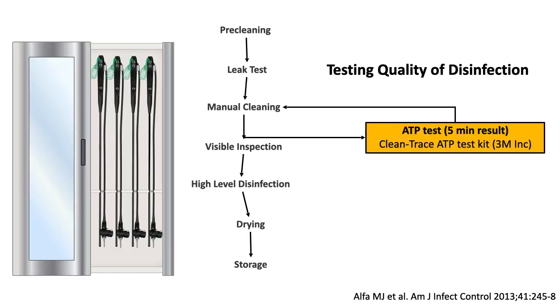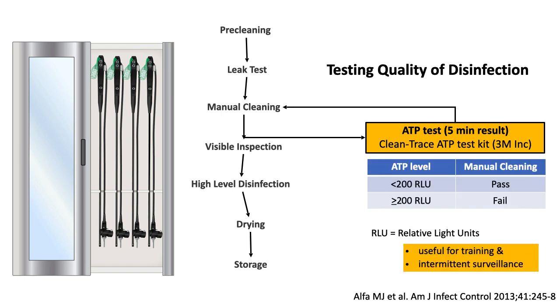So what can we do? There are several things that we can do to improve the process. One is testing for the bioburden. That is, once you do the leak test and the manual cleaning, you check for ATP. Biological material has ATP, and if you test for ATP, that means there is bioburden. It takes only 5 minutes, and if it is a pass, you go to the next step. If it is a fail, you go back and do the manual cleaning.